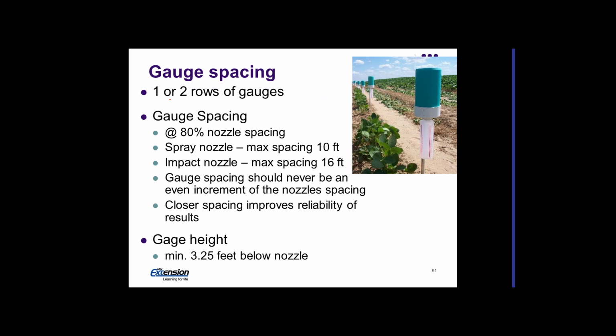So this requires 1 or 2 rows of gauges or cans. We want the spacing of these cans to be set up at 80% of the nozzle spacing. If they're always in the same spot between the nozzles, we're not necessarily going to see the variation we're looking for. So typically with a spray nozzle, we're going to put it at about a 10-foot spacing based on the nozzle spacing.